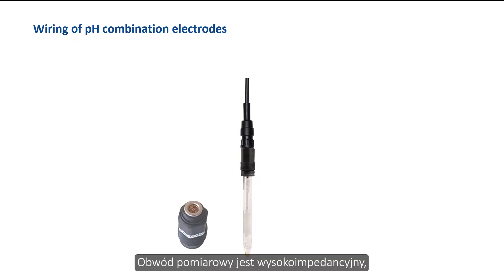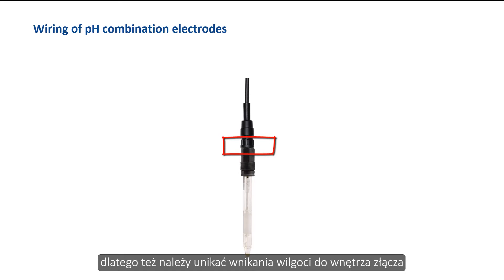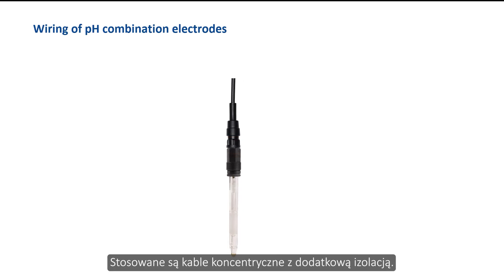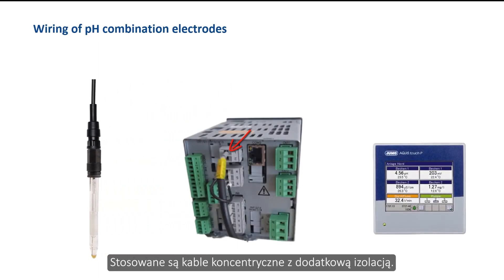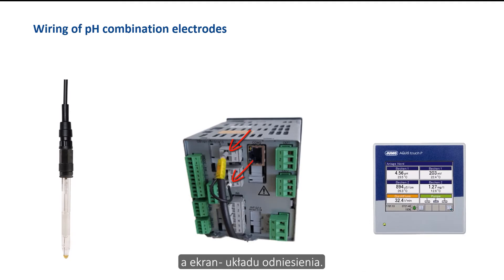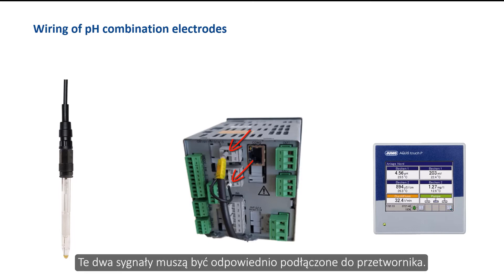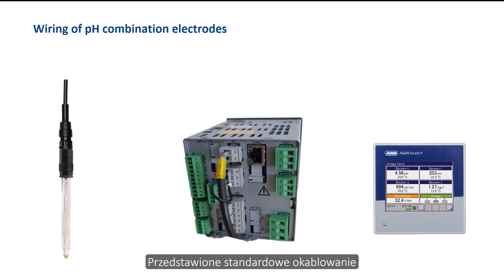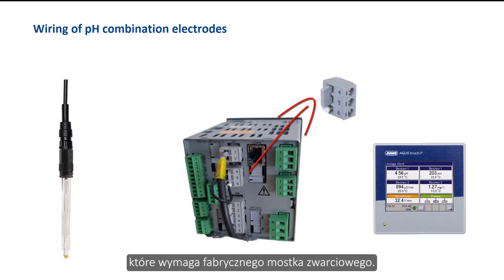The measuring circuit is very high impedance, which is why moisture penetration into the connectors must be avoided, even during installation. Coaxial cables with additional insulation are used. The inner core carries the potential of the measuring system, and the shielding carries that of the reference system. The figure shows the connection of a pH combination electrode to analysis input 1 of the JUMO AQUIS touch P multichannel instrument. The standard wiring corresponds to the asymmetrical connection, which requires a factory-fitted short circuit bridge.